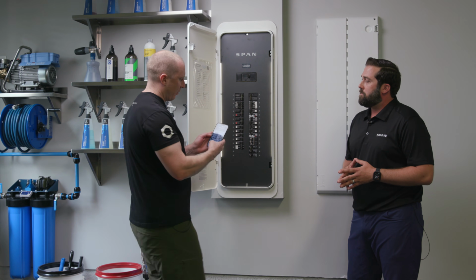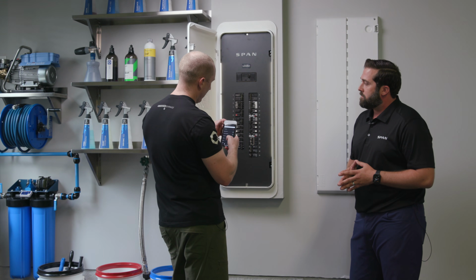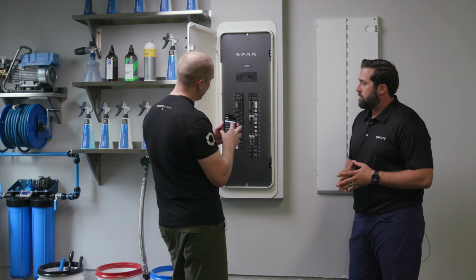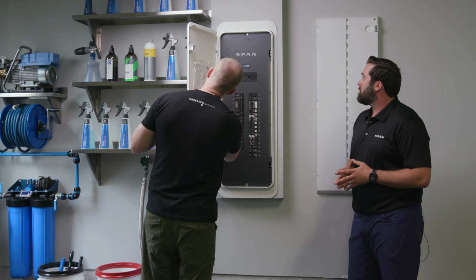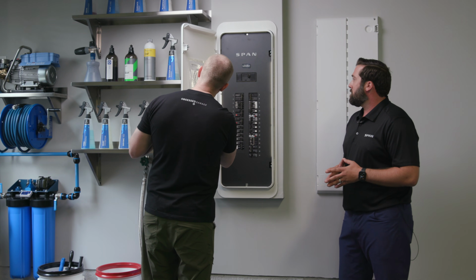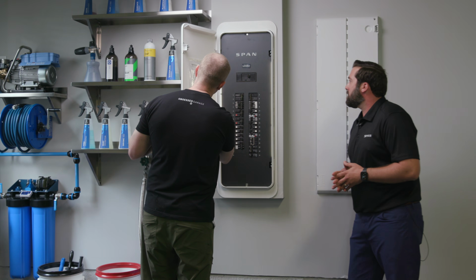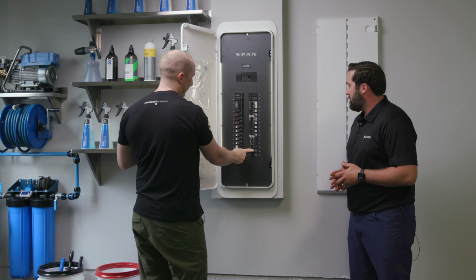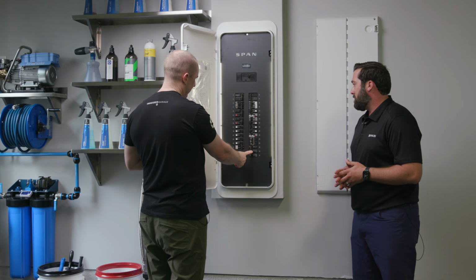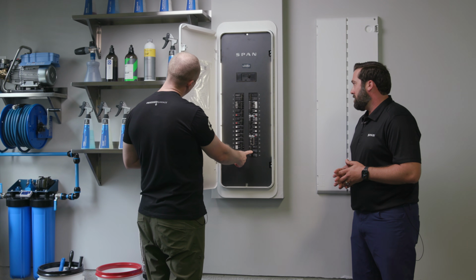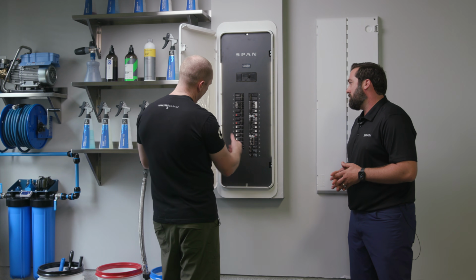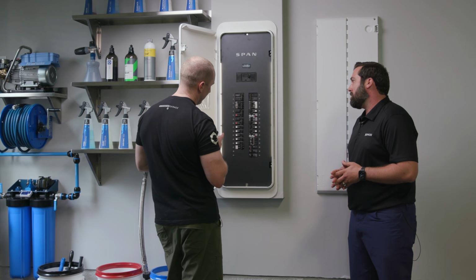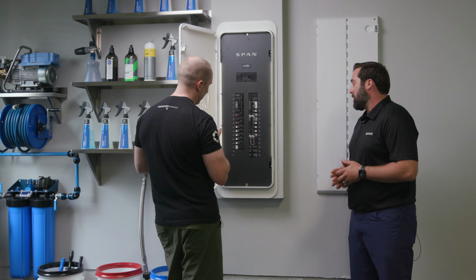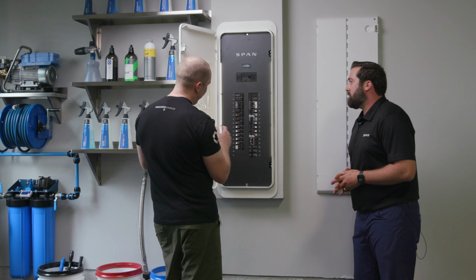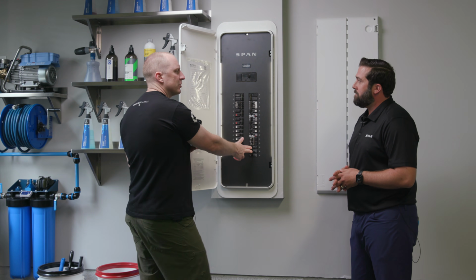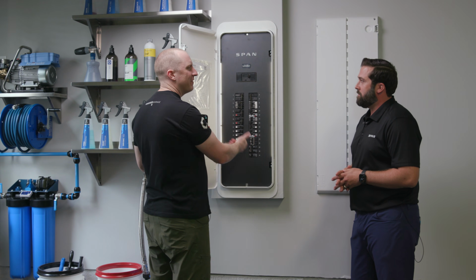Let's say I wanted to turn something off - so my Tesla charger is off. It's labeled here, which I love, 28 and 30. I have a 50 amp here - I don't know why we didn't do a 60, I don't know. Mike might have done a 50 because I think we ran number 8 wire, not number 6. That makes sense. So it's off, but my breaker's still on - it's digitally off, but physically on.